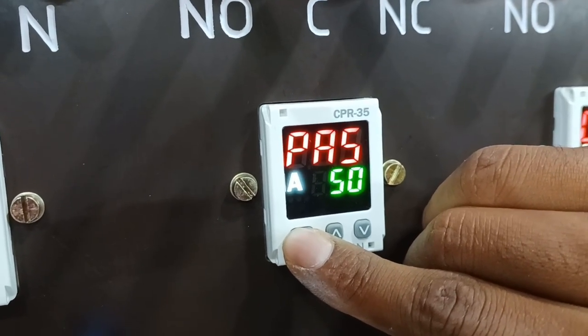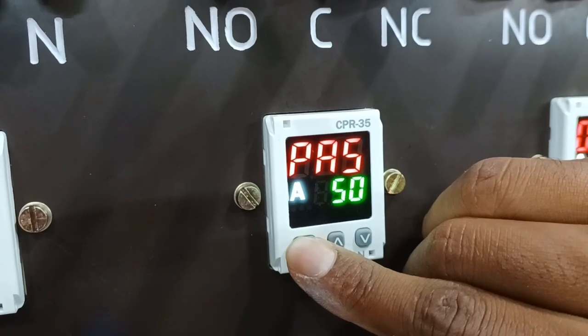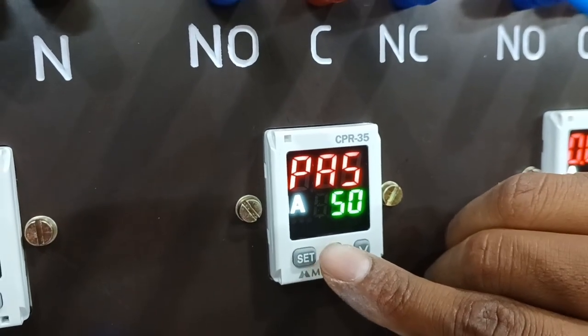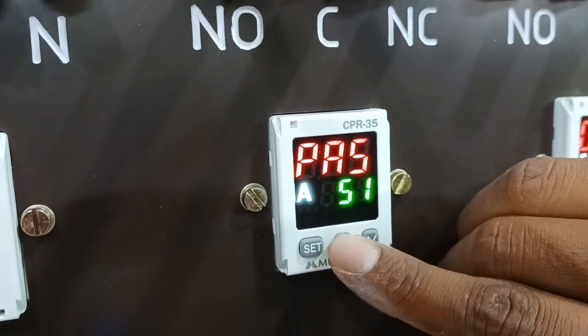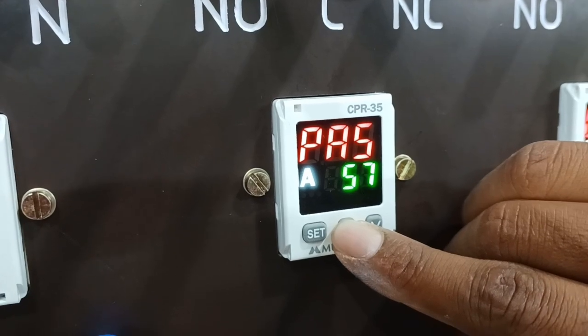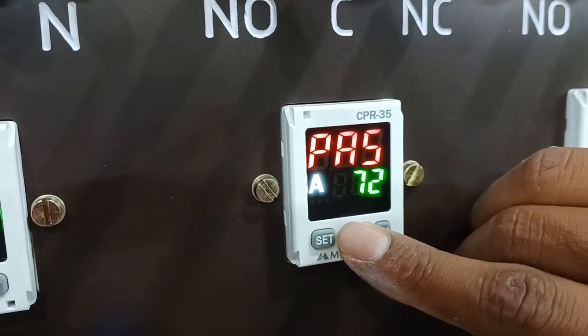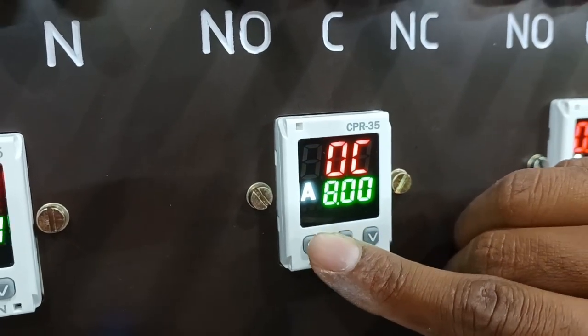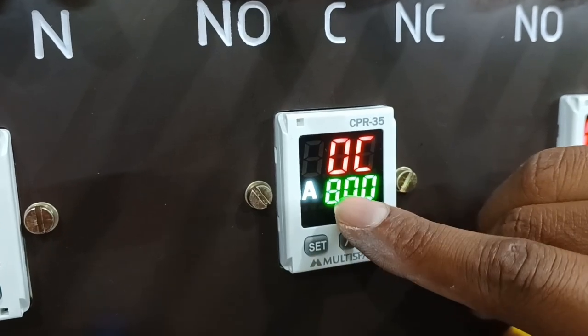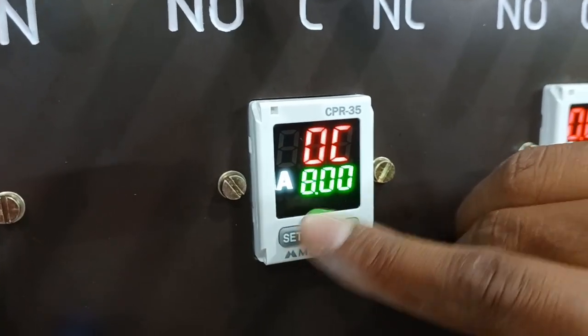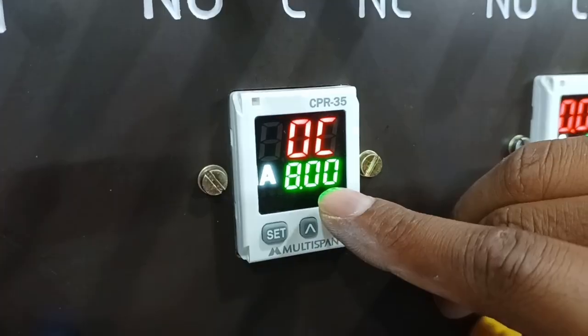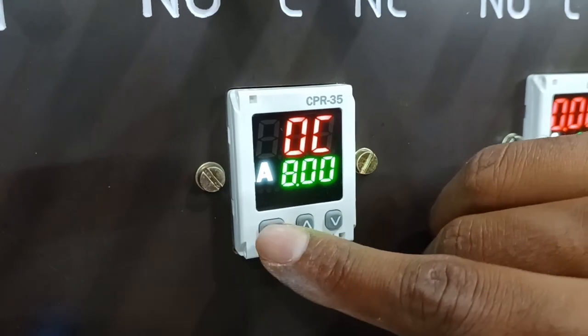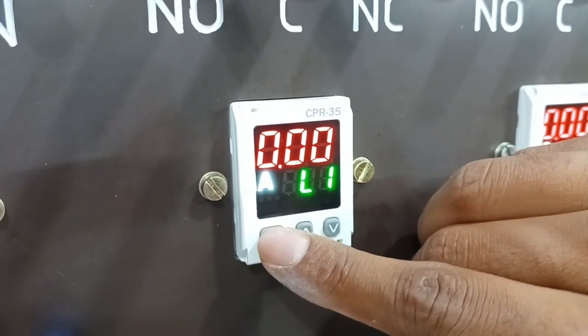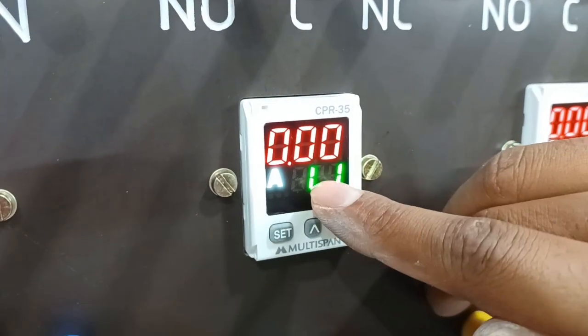Now we are setting trip value percentages. For setting trip value percentages, we need to enter password 73. So this is password 73 we have entered. Now you can find out overcurrent setting. This is 80% of the CT primary current. My CT primary current is 10 ampere. So it is 80% we have programmed for overcurrent.